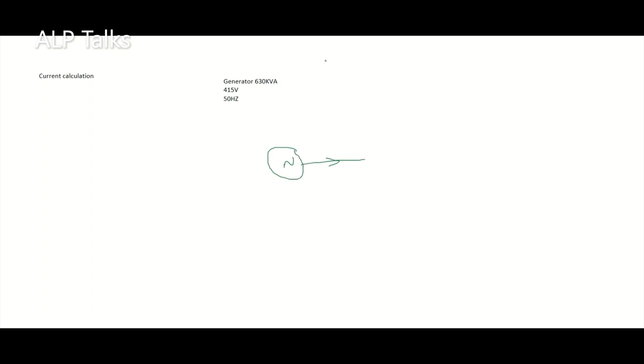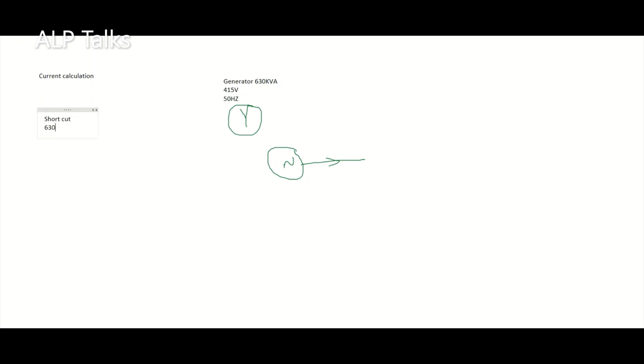What will be the current passing through the generator terminals? Generators are mostly star connected. The shortcut is simply: multiply the kVA by 1.39 and you will get amperes.